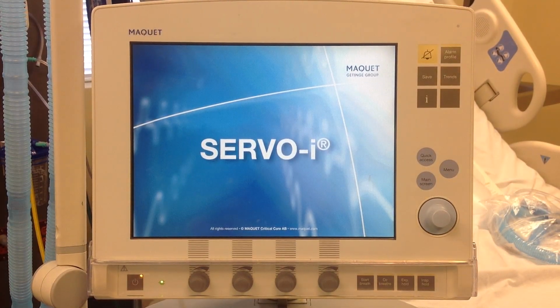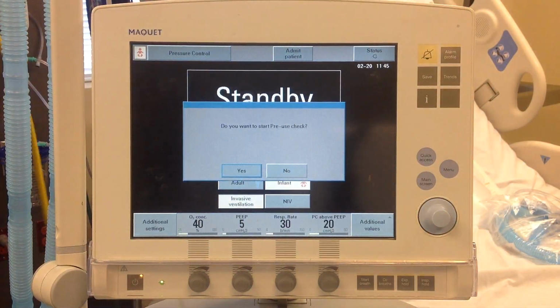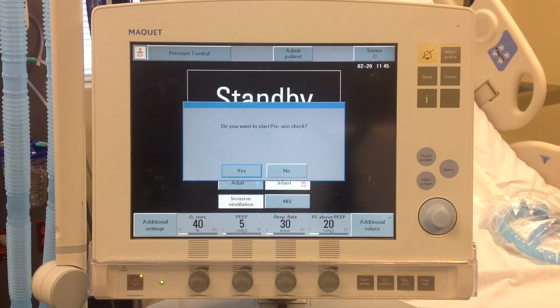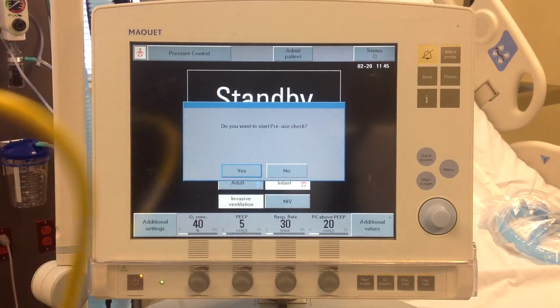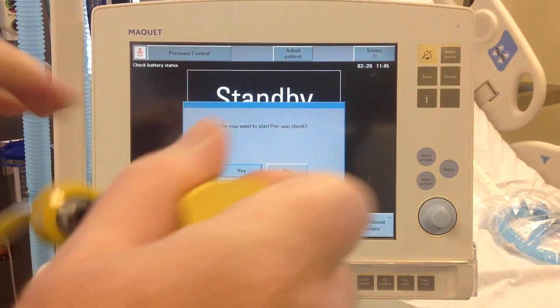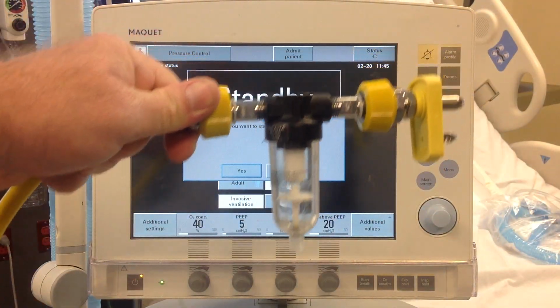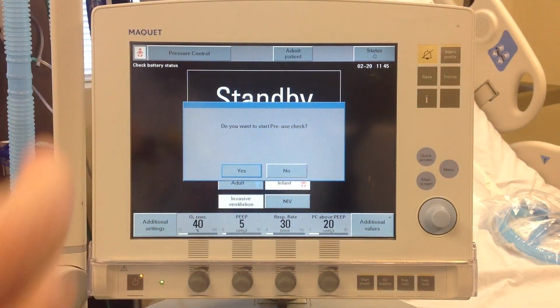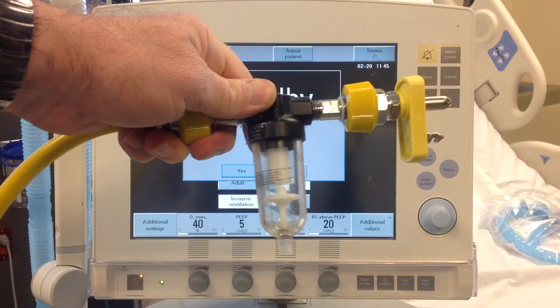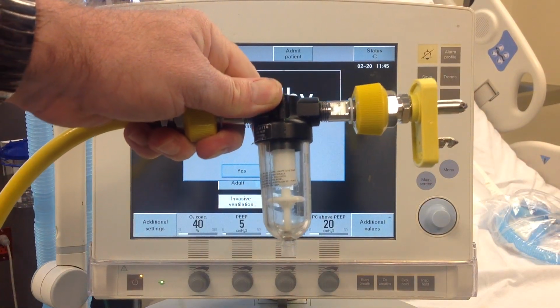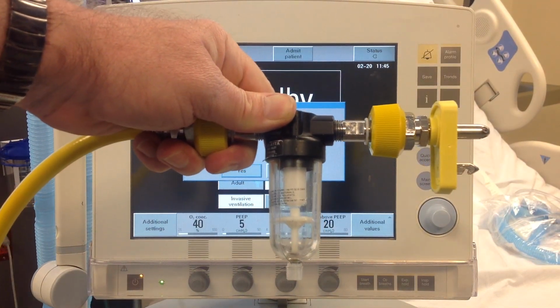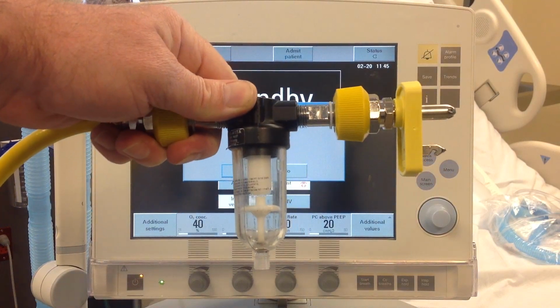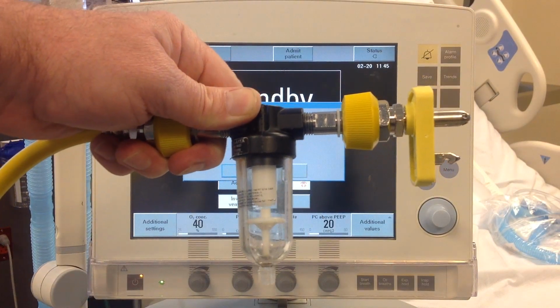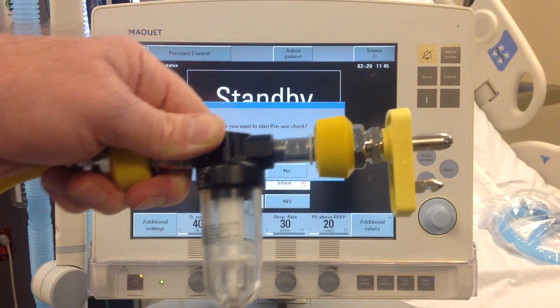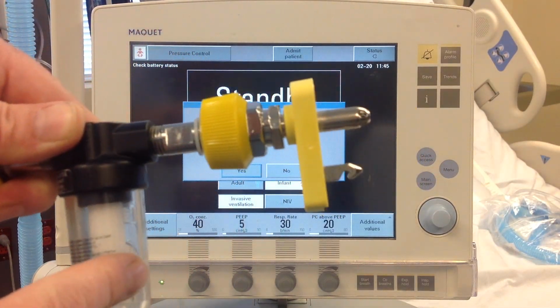Want to show you one item while we're waiting for the machine to power up, and that is this device right here. This is your air hose, but if you look at this device right here, remember from foundations, how do we get our air for the hospital? It's through a compressor. Even though there's a desiccation or a drying agent that's supposed to get all the water out of the air, there's a possibility of water coming through, and this is a water trap.